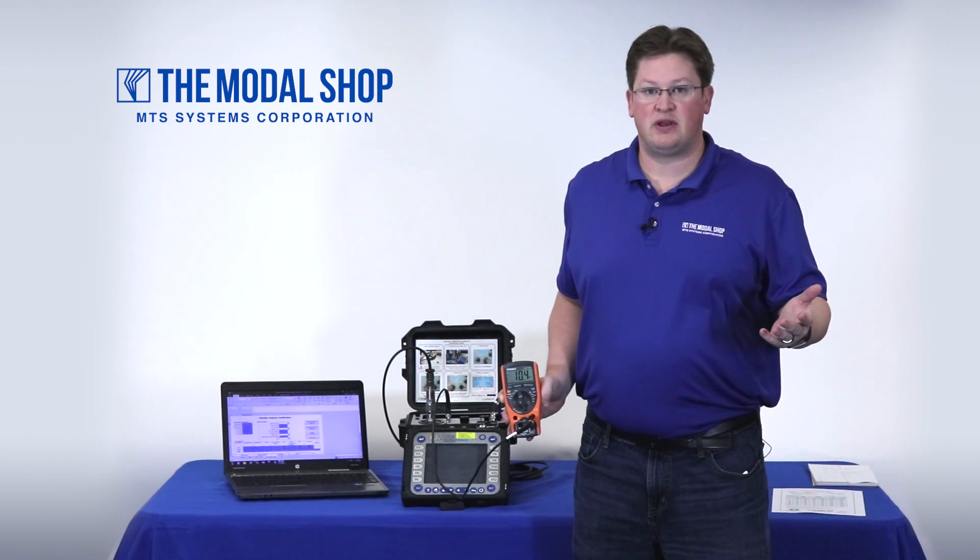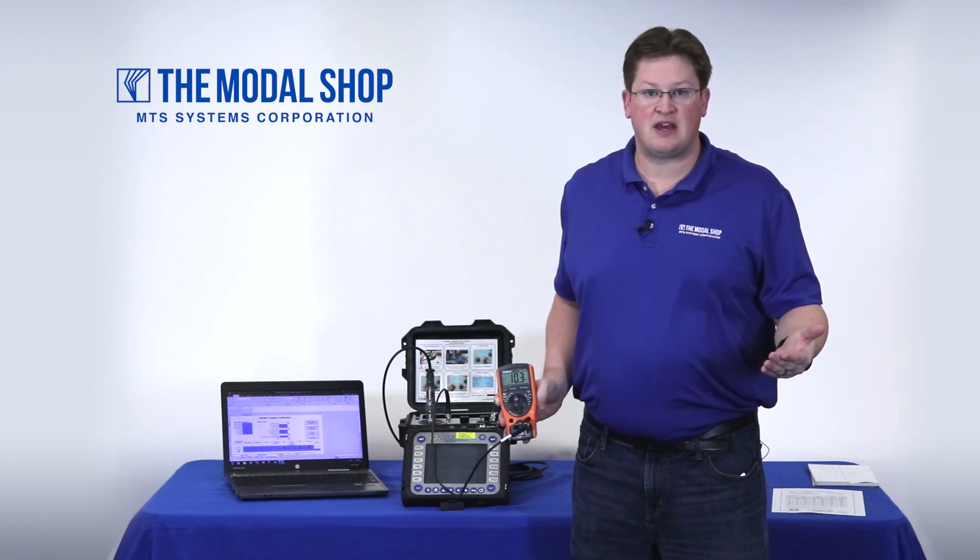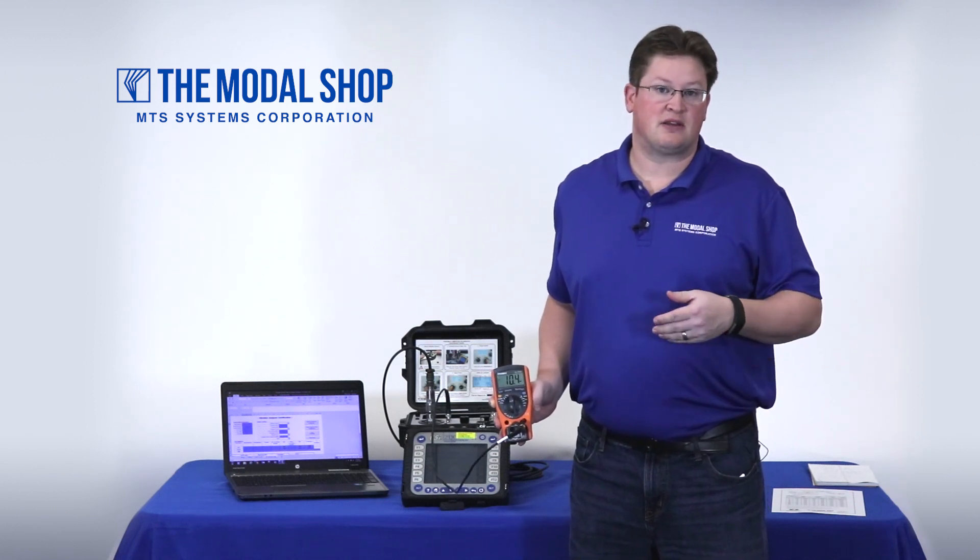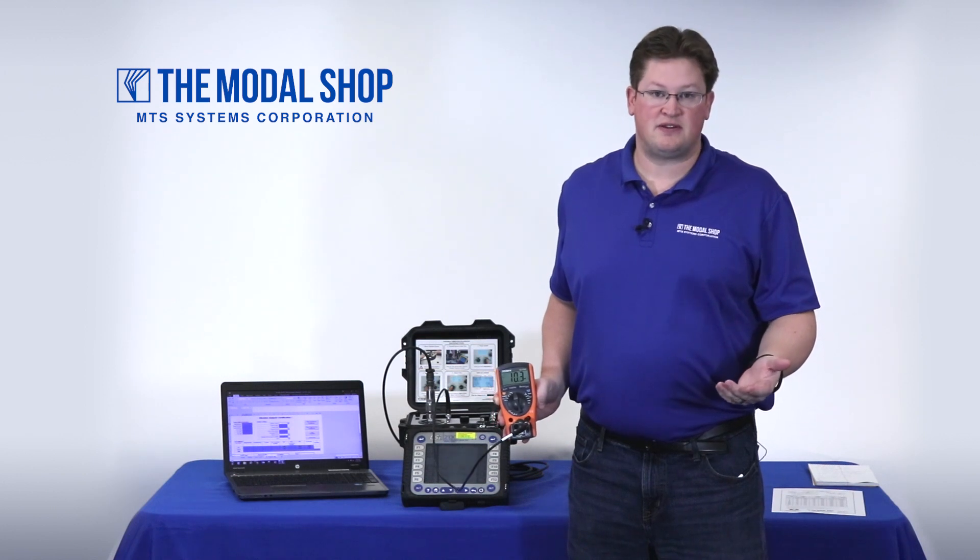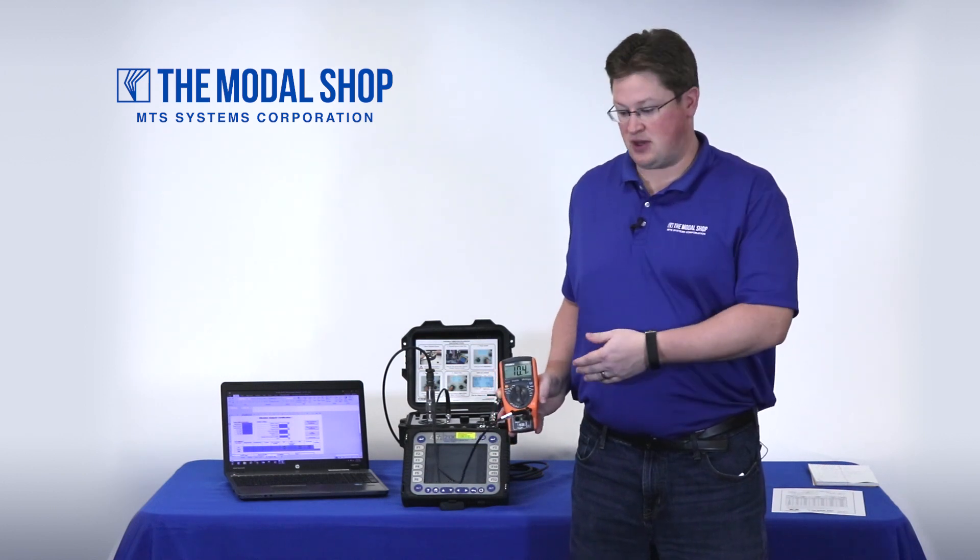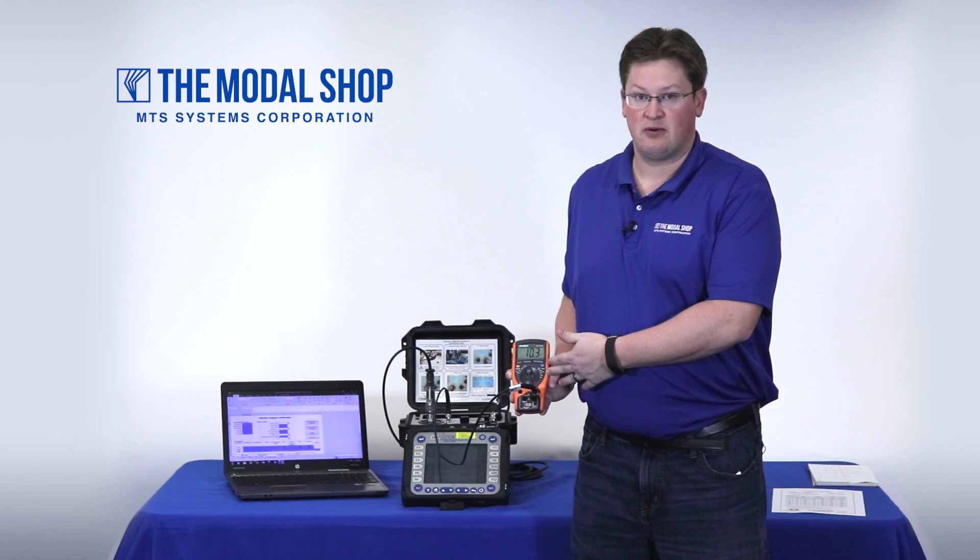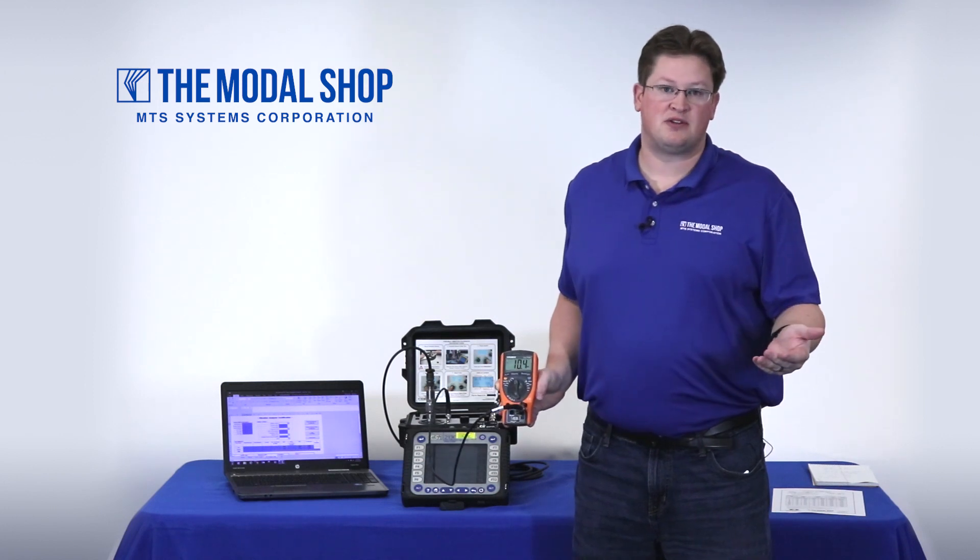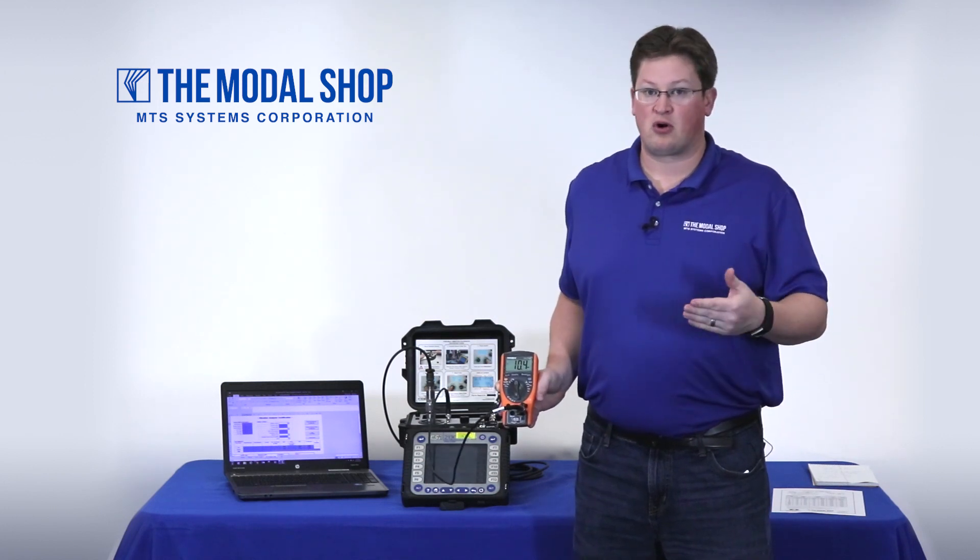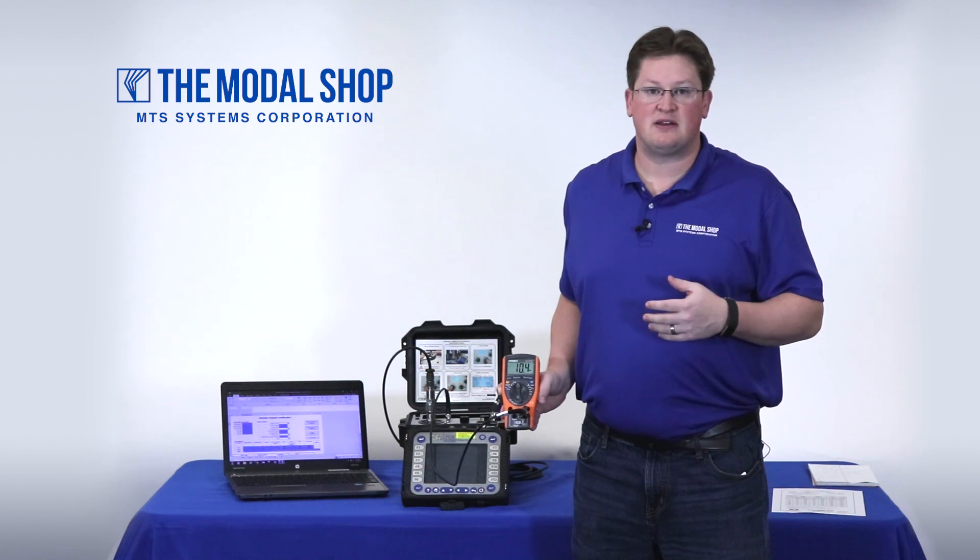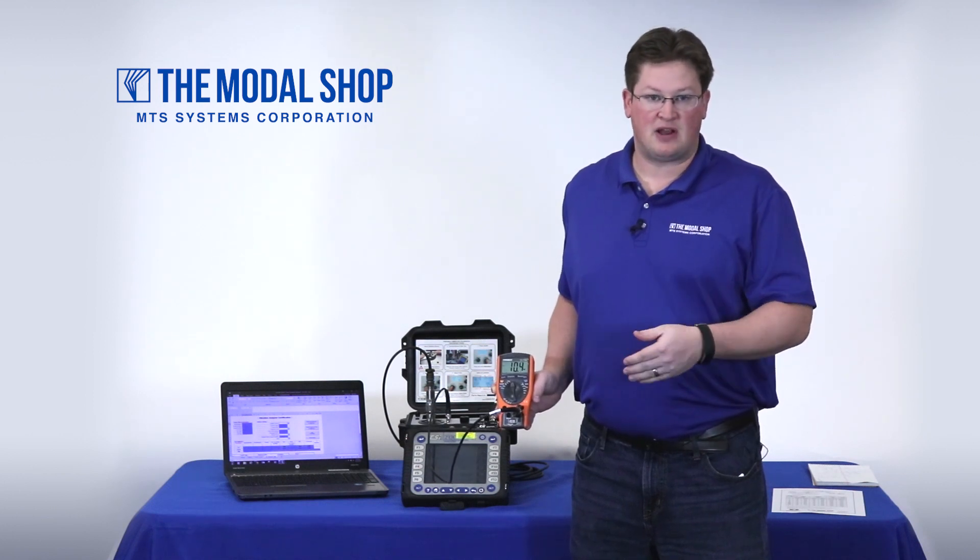The other innovation is the ability to ensure the accuracy of the calibrator by testing the reference accelerometer that's inside the shaker, which I'm doing here with an independent voltmeter.